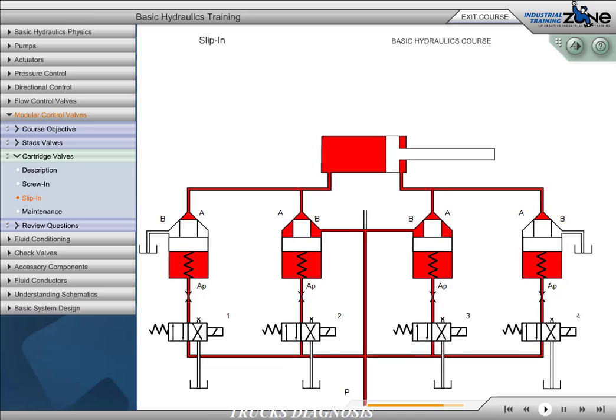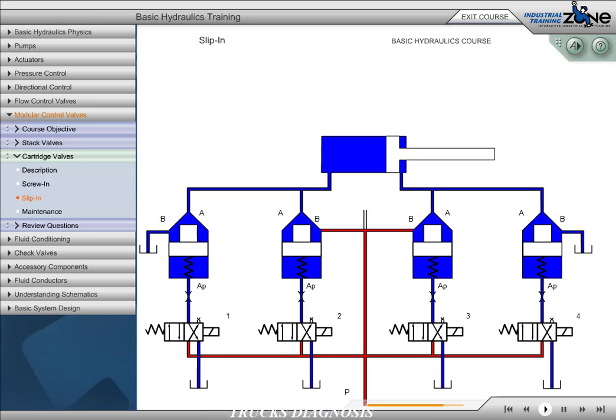Energizing all four valves will cause the P, T, A, and B work ports to be in common or open to each other. This will allow pump flow to return to the tank and the cylinder to float.